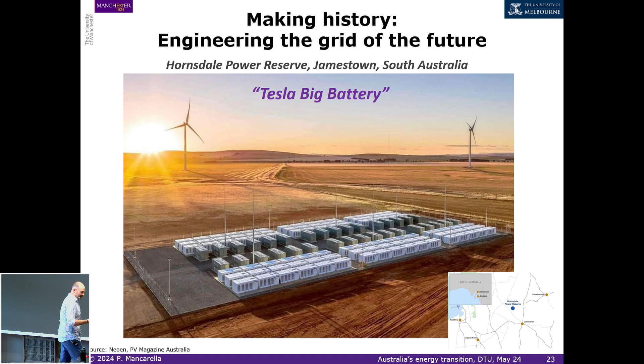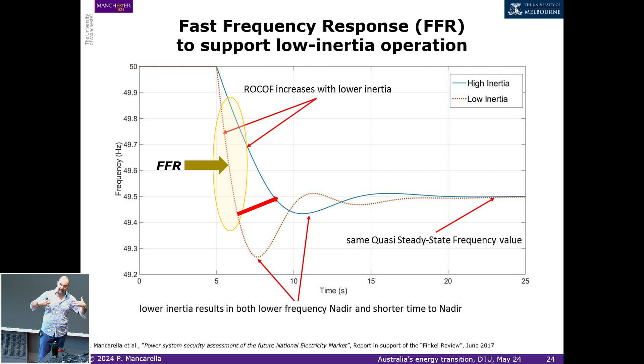Effectively, the idea is that with some fast frequency response from batteries, you can try to push back that frequency response to a kind of high inertia grid. Eventually, if I do not have enough synchronous inertia that I can inject into the grid, can I replace it with some form of very fast injections? That is what the batteries would do. Of course, the physics will not work exactly like this, but this is the principle.